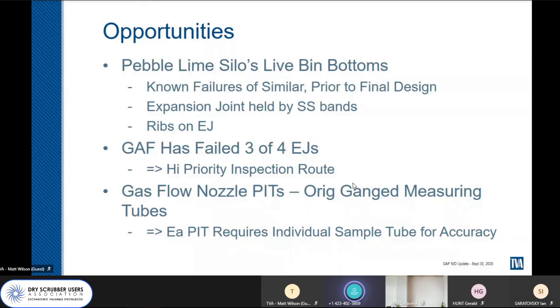Gas flow nozzle pressure indicating transmitters, that's in the inlet duct. Originally all the measuring sample tubing was ganged together, so the lesson learned there is that it did not provide good accuracy, so we had to go back with individual sampling tubes.